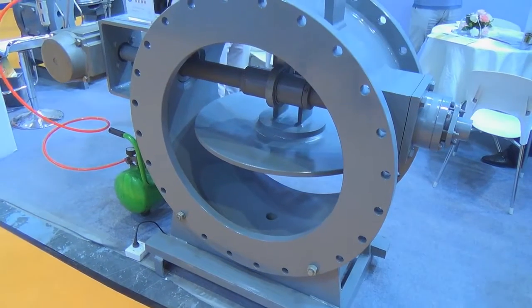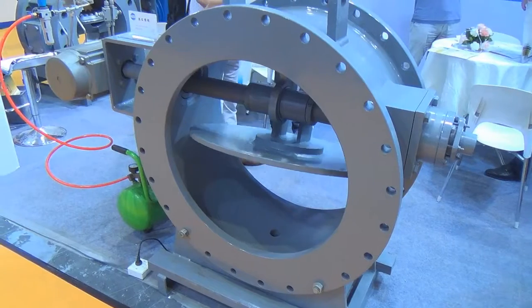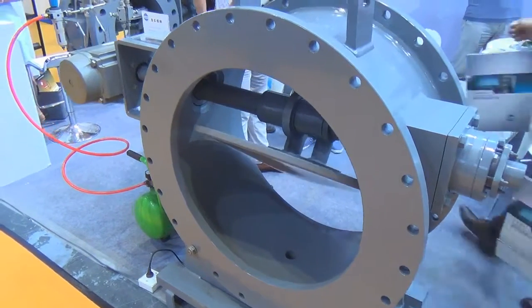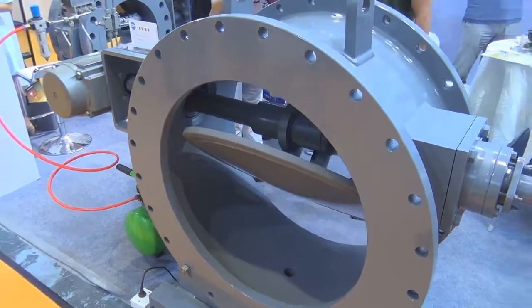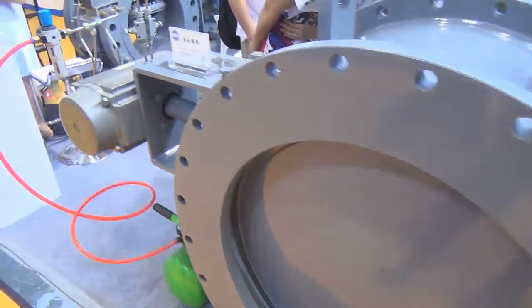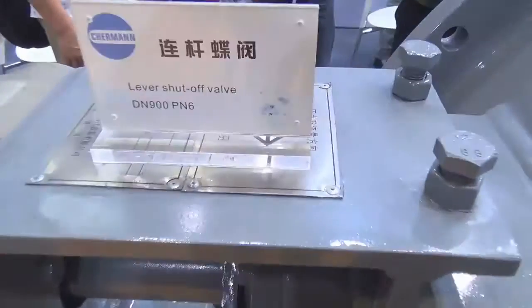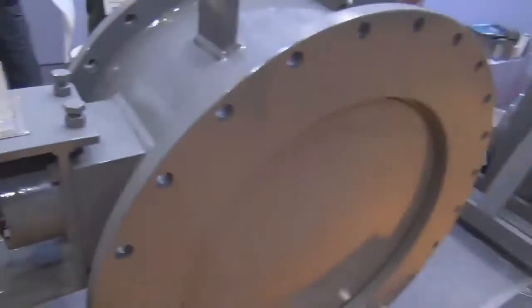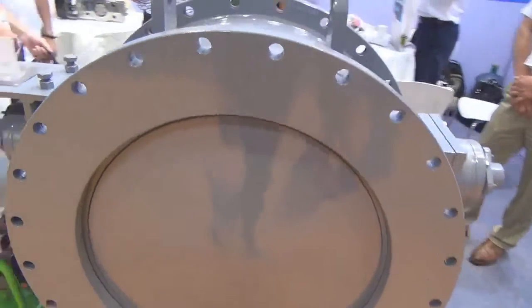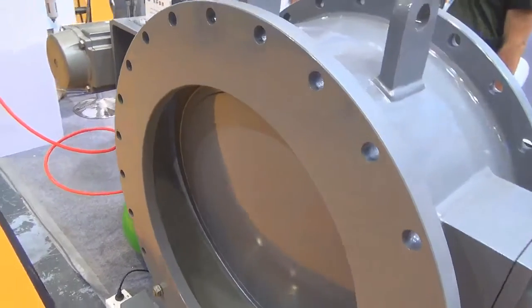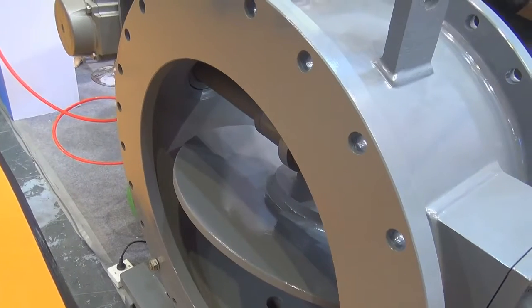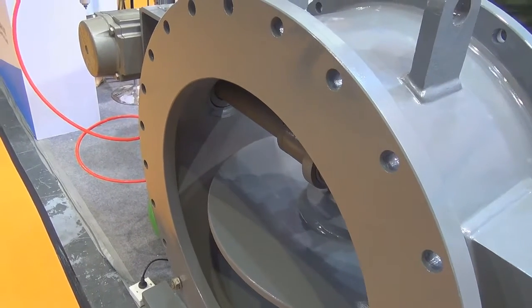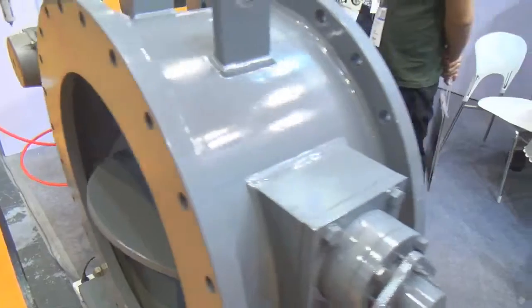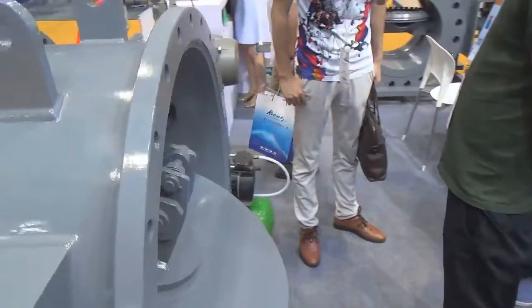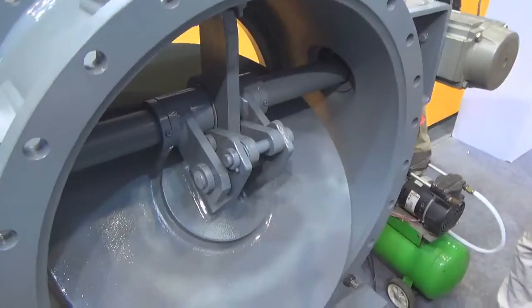In the butterfly valve industry, except for the triple offset butterfly valve, we actually have another kind of butterfly valve. When we open it, it has no rubbing. This valve is called a lever shut-off valve. When the valve is going to open, the valve disc will immediately leave the valve seat. So the valve disc will not grab the valve seat. When we open the valve, there is no rubbing between the valve seat and the valve disc.